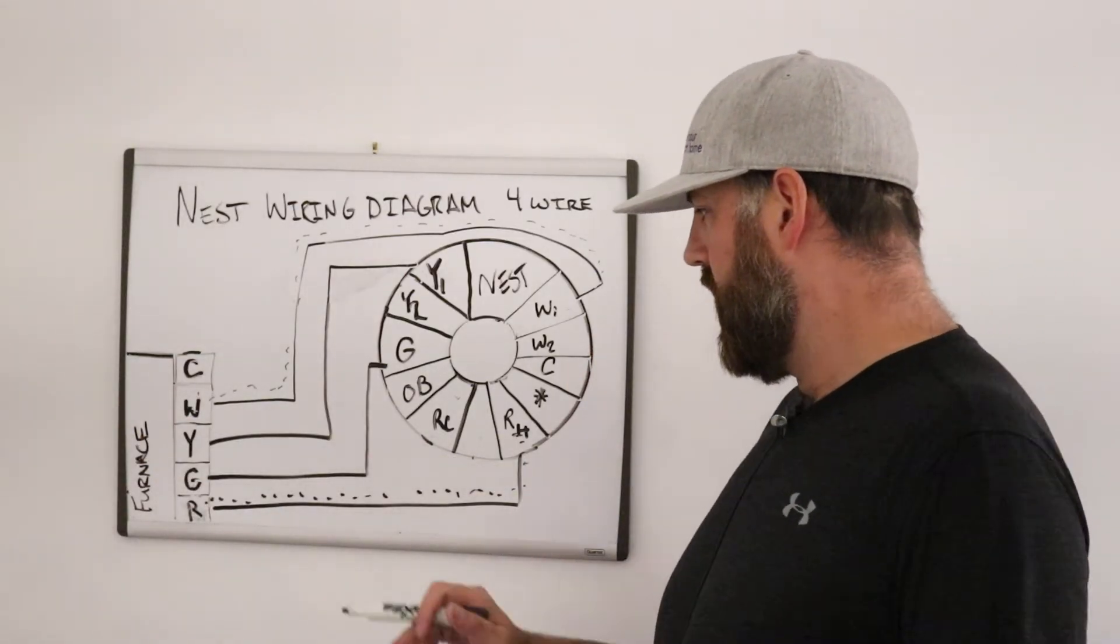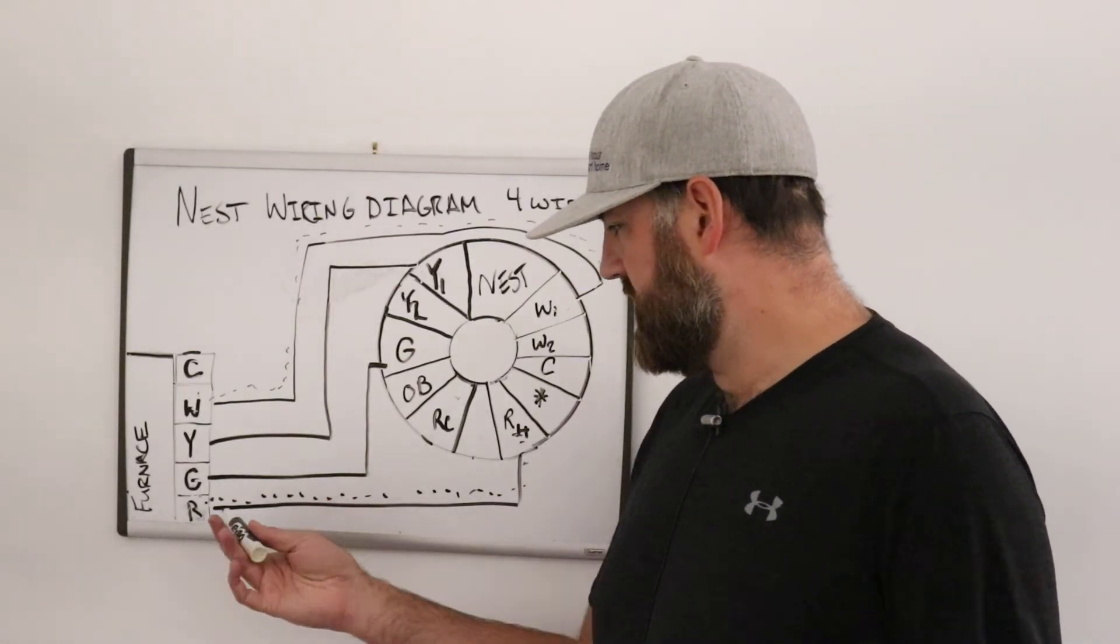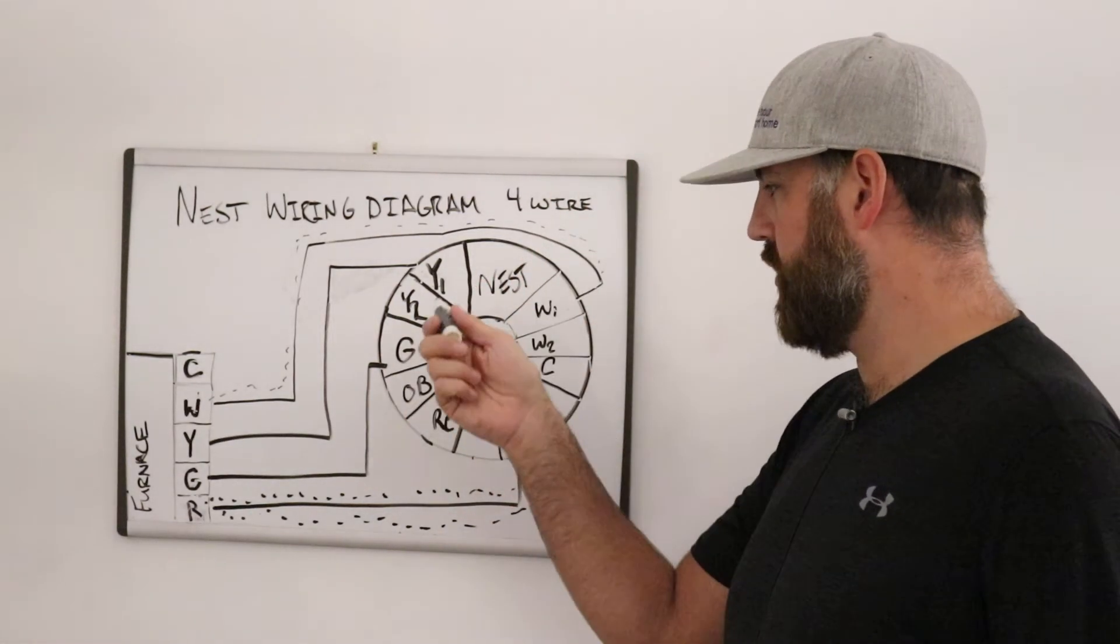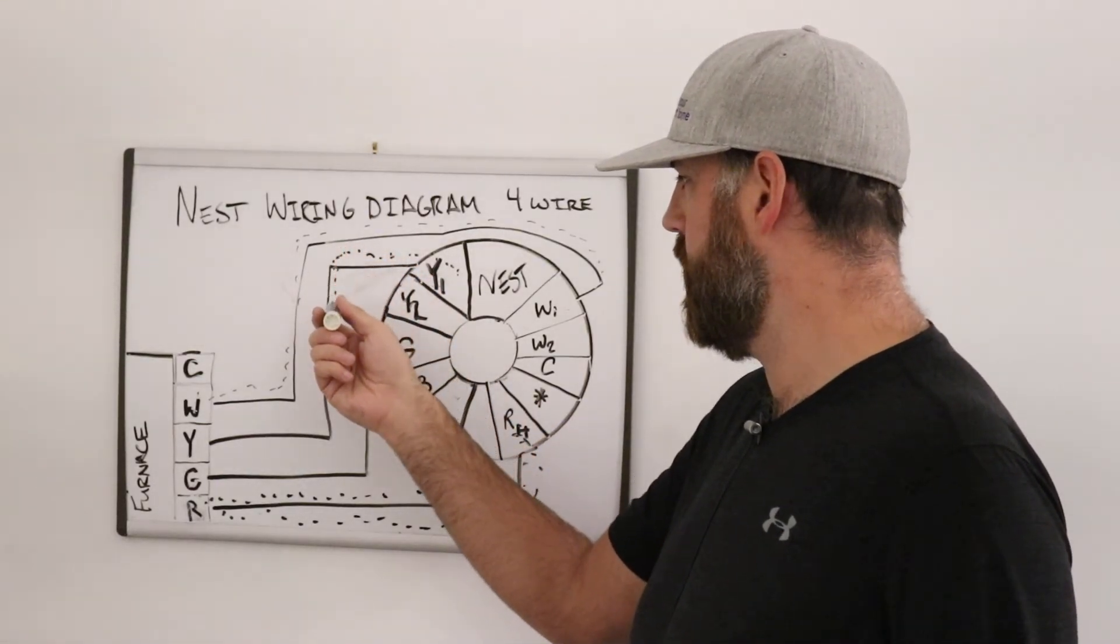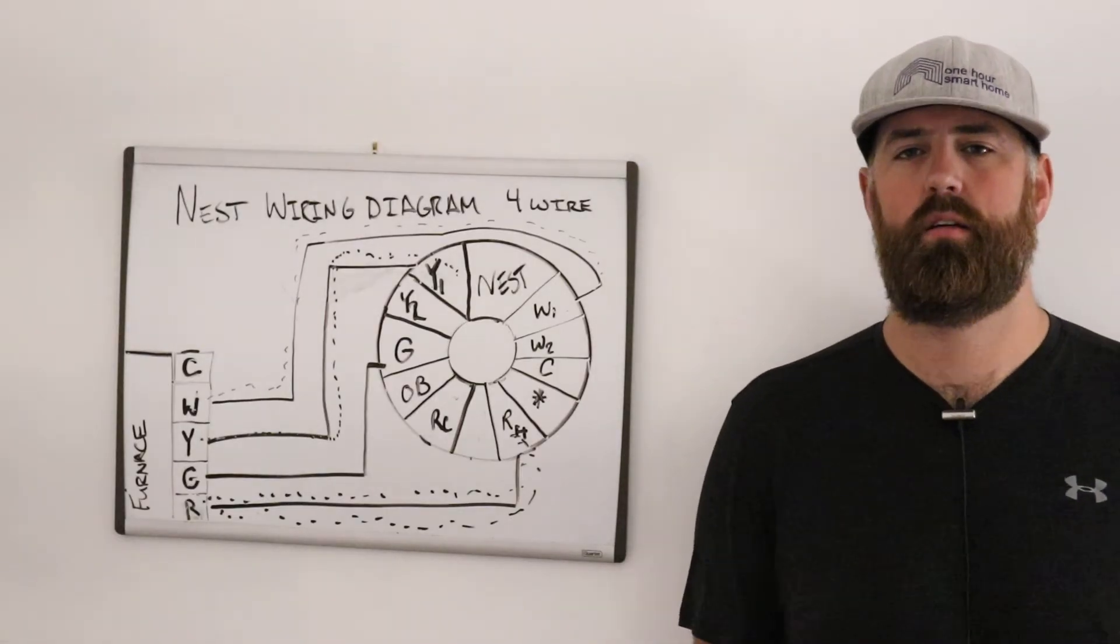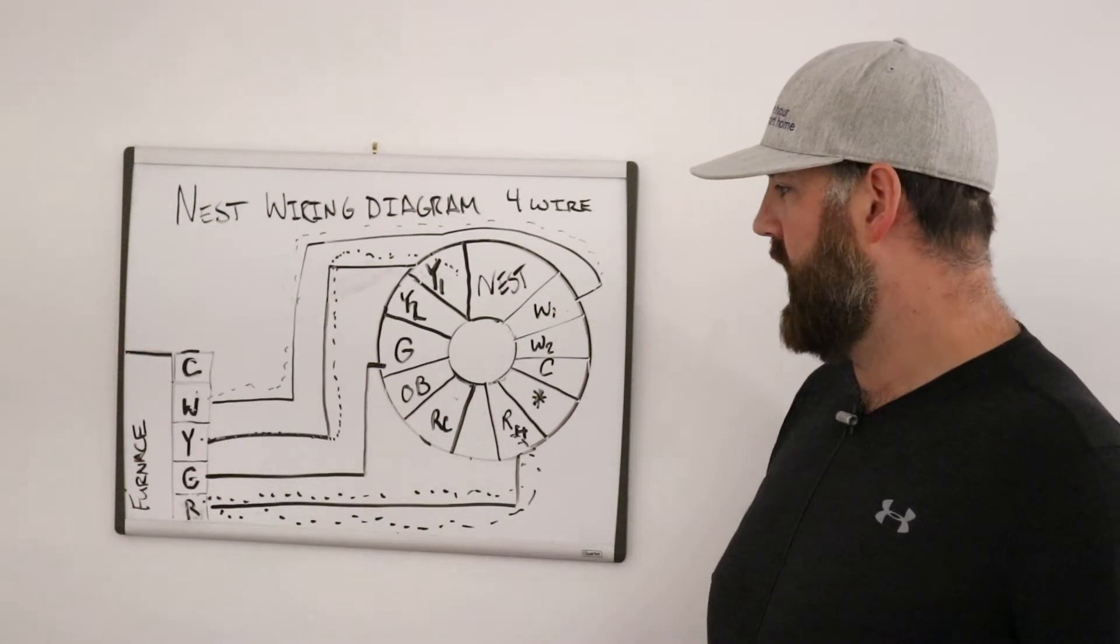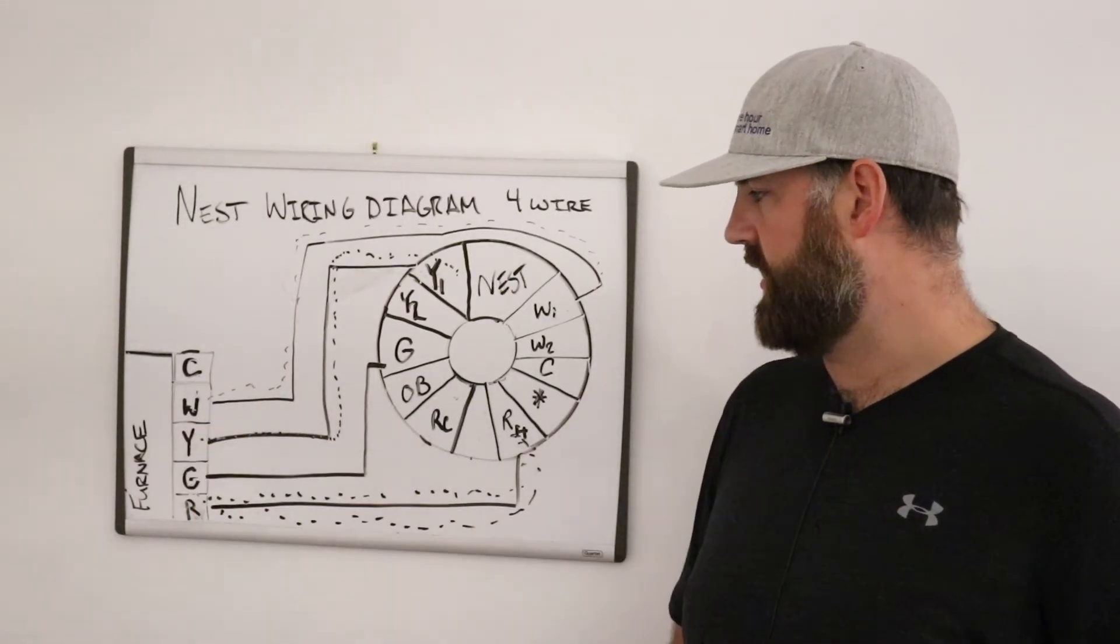But if you were calling for air conditioning, so you've got it turned down to 50, it's a very hot day in the summer, what you would still have is power coming from the R, power always comes from the R, goes through the RH into the Nest, and then the Nest says, okay, cooling. It closes the appropriate internal circuit inside here. And then power goes back down the Y1 terminal, the yellow wire, Y, and it goes down to the Y terminal on the furnace and it turns on your air conditioning.